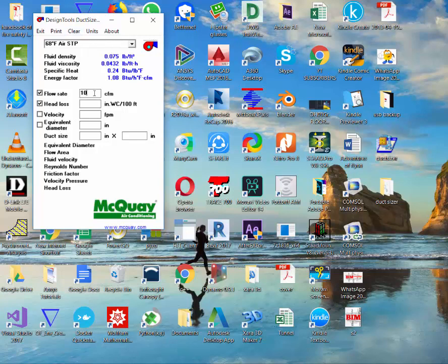Suppose you have a flow of around 10,000 CFM and you want to do it for a head loss of 0.1 inches of water gauge per 100 feet.